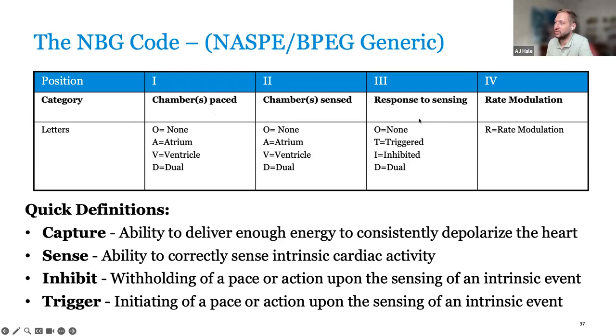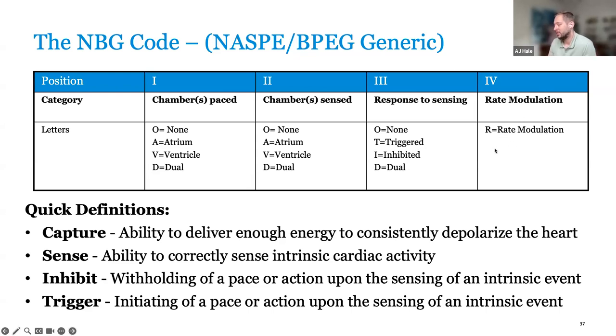The third position is the device's response to sensing: O means no response, T means it triggers pacing, I means it inhibits pacing, and D means it does both. The fourth position is rate modulation — added later — which is the ability for the device to respond to a sensor-driven rate. For patients with chronotropic incompetence, it allows the device to pace physiologically appropriate to the patient's need; if the heart doesn't modulate its rate itself, the device can do it.